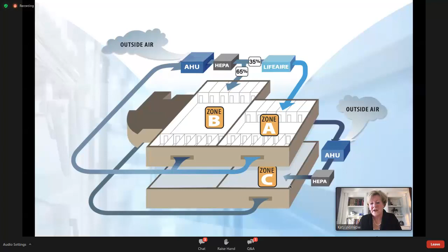In Zone A, these 16 rooms were completely protected by the LifeAire system. So all of their supply air and all of their return air, all of the air in these 16 patient rooms, was provided by our technology. The second half of the floor, the second 16 rooms, 32 in total, served as a control against Zone A. So they were pure HEPA filtration, your typical gold standard, but did benefit from the return air coming from the LifeAire protected zone. And then our pure control, if you will, was the entire floor beneath that.